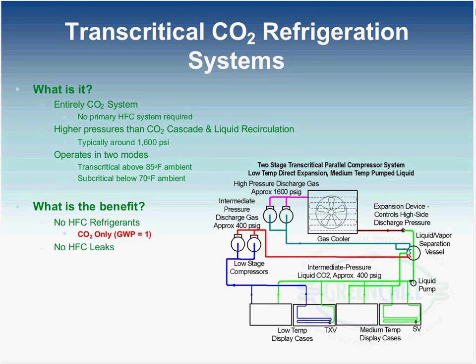Another thing with CO2 on the transcritical side is we actually don't condense the CO2 in a condenser like you normally would see in a regular traditional type system, where you have an air-cooled condenser on the roof where we turn the discharge vapor into a liquid and then circulate that liquid throughout the display cases in the store. Here, when it's in a transcritical operation, we just cool the gas. It's still a gas when it goes in and still a gas when it comes out, but we've removed some of the excess heat and reduced the temperature some before we circulated that through the store.